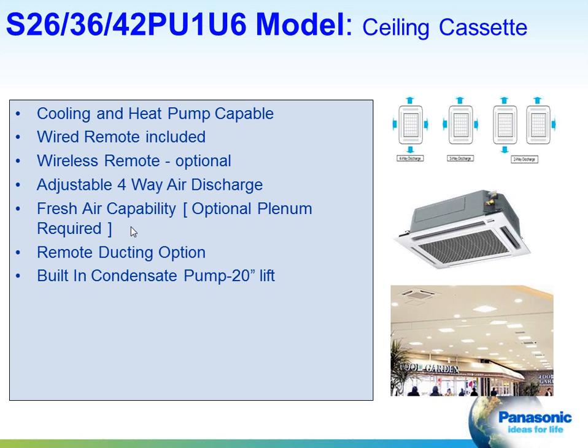A very popular unit here is a ceiling cassette. And again, it comes in both cooling only and heat pump. It comes with its own wired remote, with wireless as an option. Adjustable 4-way discharge. The 4 louvers on this unit can operate in the swing mode, or they can be fixed as well. You can introduce fresh air, and there's an optional plenum kit that you need to purchase to accomplish that. And you can duct off this unit.